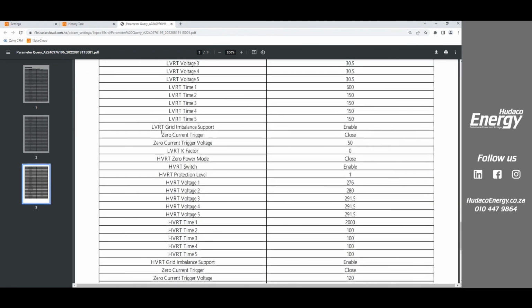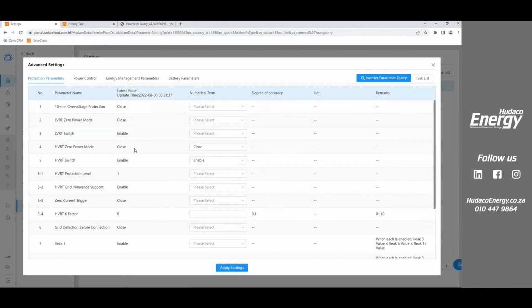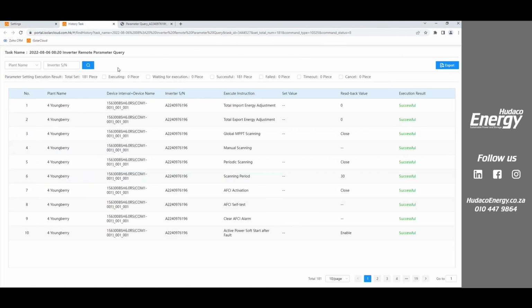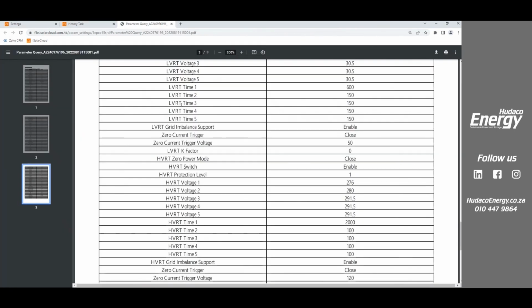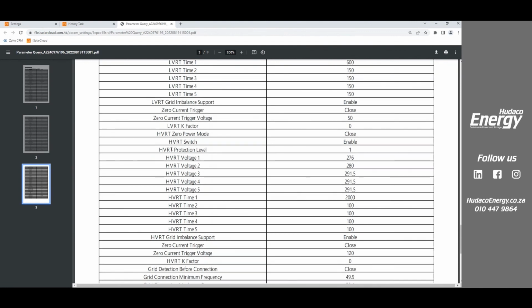Okay, here's this high voltage ride through that we were looking at here. So what I've done is on my high voltage ride through, normally, if you remember earlier, it said protection level is 3 for South Africa, right? That's the standard, is protection level 3. I've changed my protection level to 1.